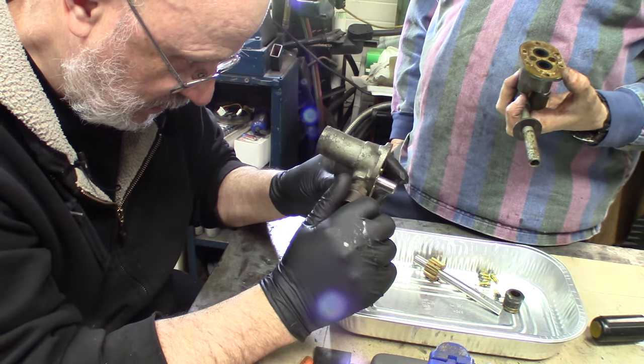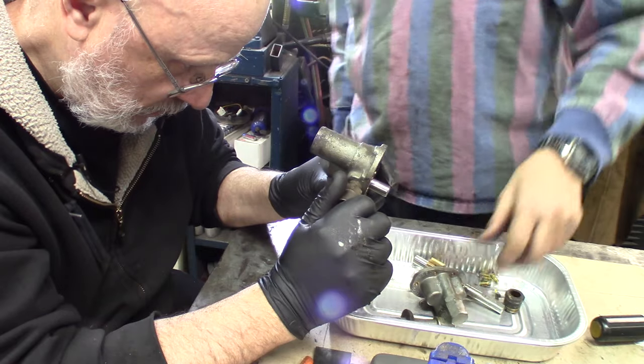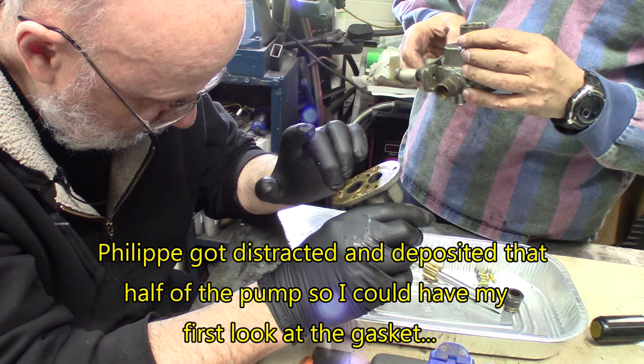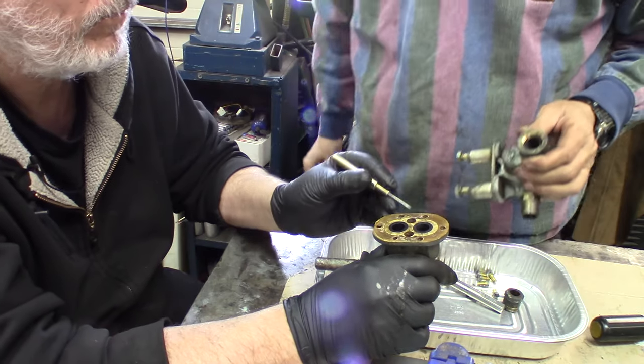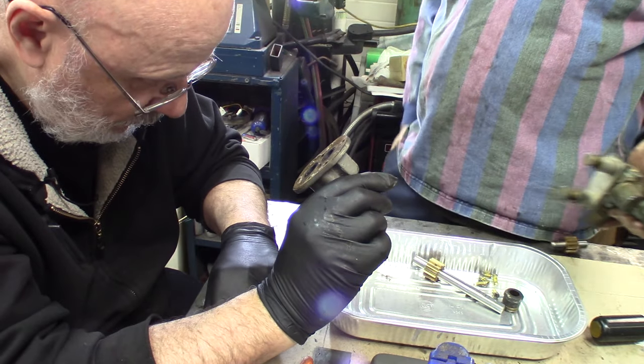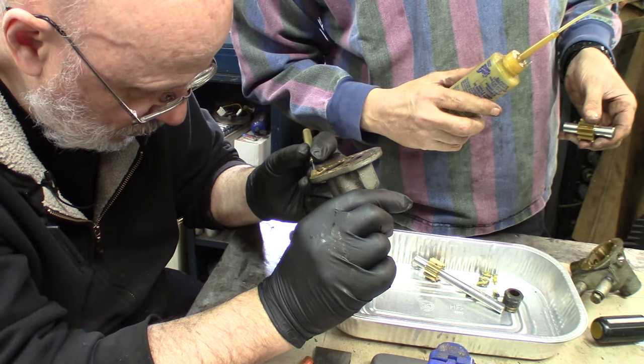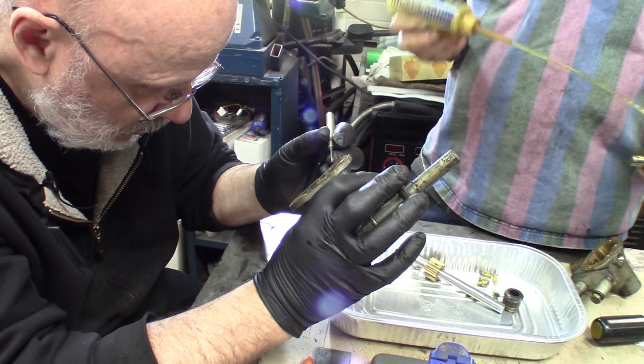This gasket doesn't... Well, that's a packing, though. The more you tighten it, the more it seals. I think we'll have to go for packing it again. Well, I don't know if you can pack it. I think it's a piece of rubber. The inside part's still pretty good, but the outside third is shot. I see something here. We're going to have a leak there. The Loctite sealer would do pretty good on that. It's a paper gasket. I think it's just paper. I think we can use plain paper on this one. You got to make it. Now let's...